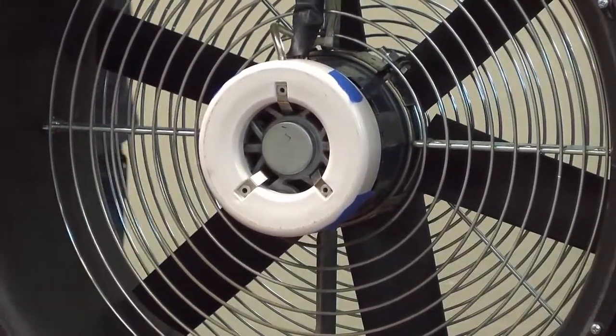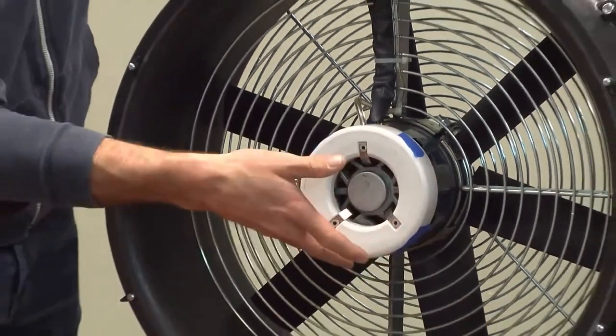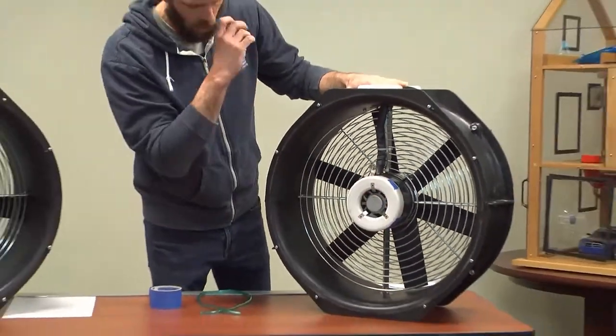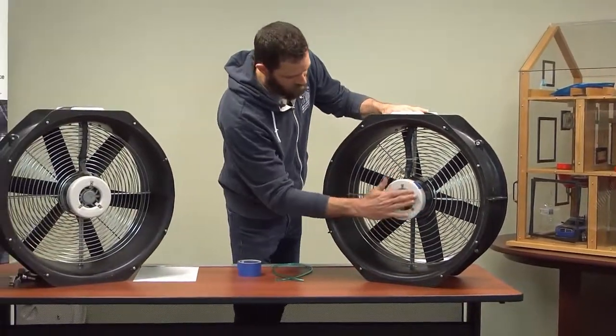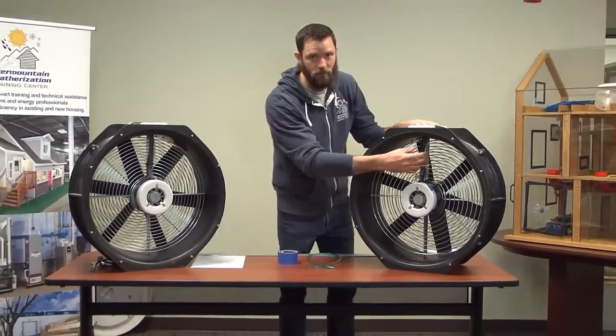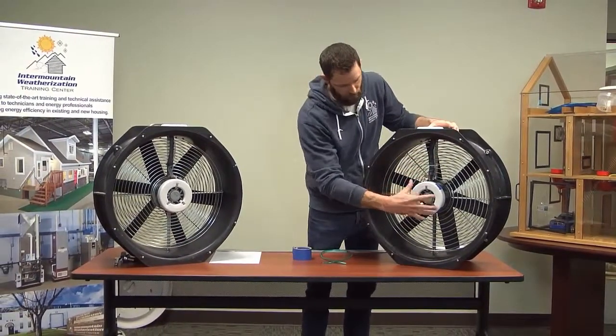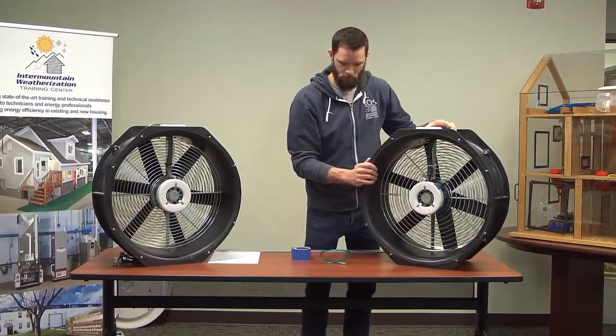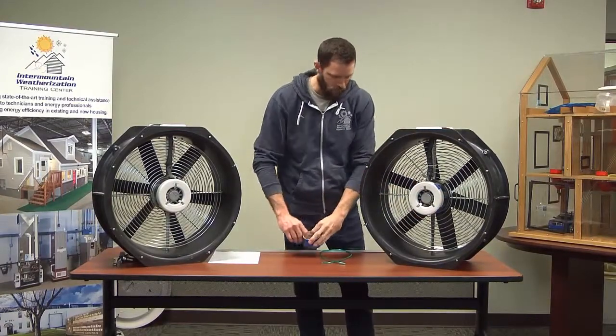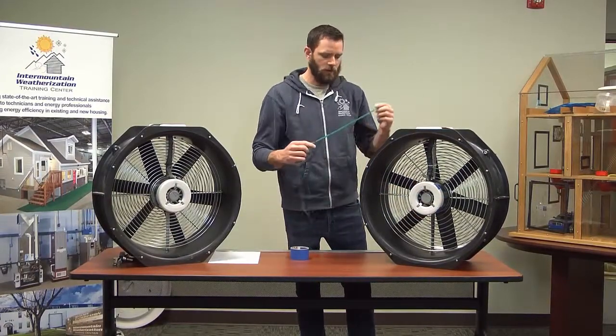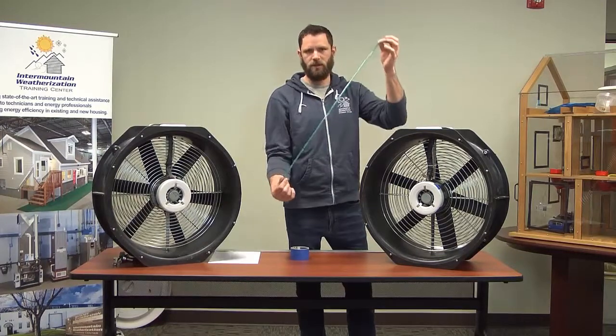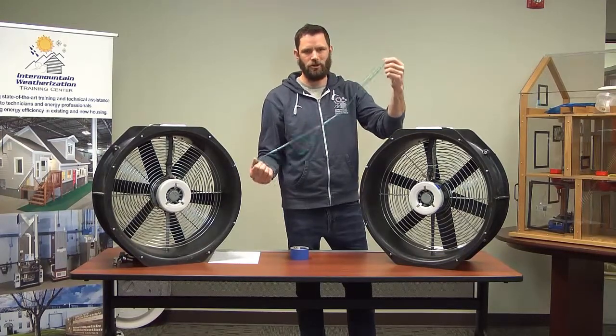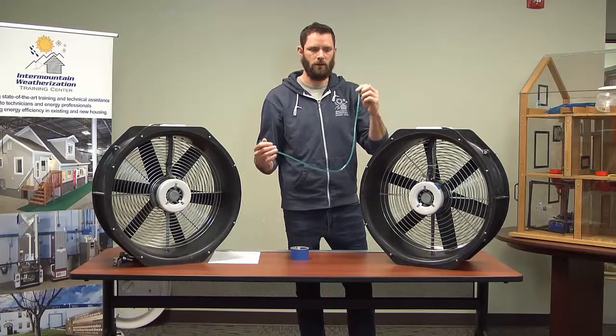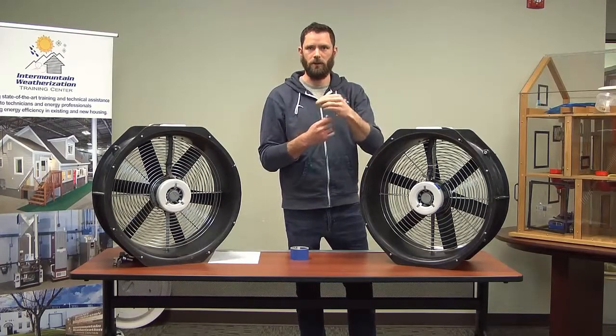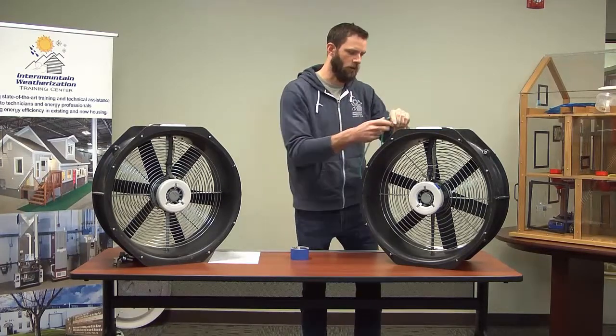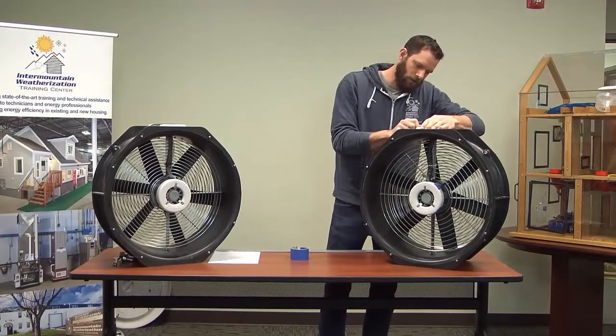All right, so I've got the four sensing holes covered with masking tape, and in my visual inspection I don't see anything that looks suspect. Everything looks good. The housing feels like it's mounted correctly, solid. So I'm going to take a piece of tubing, and make sure whatever tubing you're using during your test doesn't have a hole in it, because that could screw up your test.